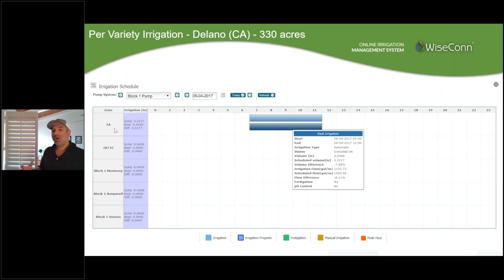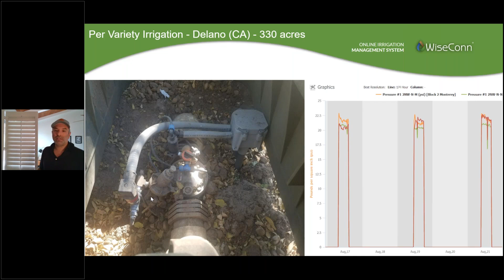And just to be sure, this is a ranch that has 75 valves on it. So these guys decided to go with a pressure transducer after each valve in order to be able to check that the pilots and the pressure regulation were constantly operating correctly according to their calculations, just by monitoring the pressure after each valve. If a valve loses pressure and the pilot is not regulating accordingly, you can't tell that until the trees start showing it. So just by being able to identify that change in the pressure regulation ahead of time, or as soon as it happens, you can correct it immediately, and the economic impact of that pays for the transducers, the service, and most of the system.